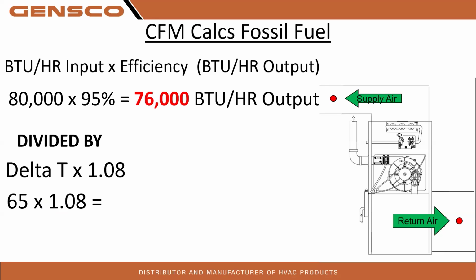Again, we are taking the return air temperature right at the unit. Supply, take it a couple feet down if you possibly can, because if we're right above that burner, and same thing with the heat strip, that's going to be a little bit higher in degrees than just a couple feet down the duct. And of course, the best way is to traverse the ductwork and take 3, right? Because the airflow is going to be coming off the top of that furnace and kind of bypassing. So this area here might not be the best to get a sample, maybe up here.